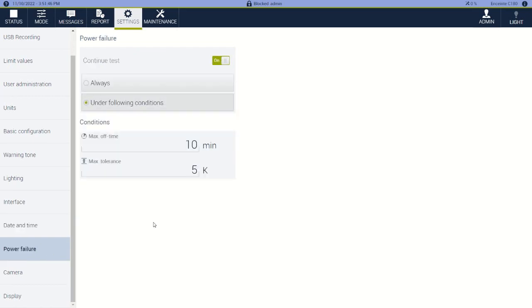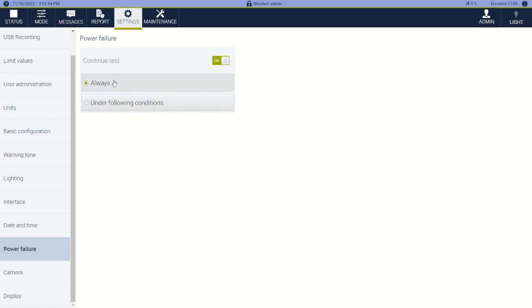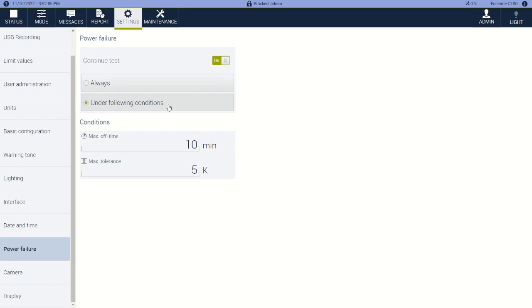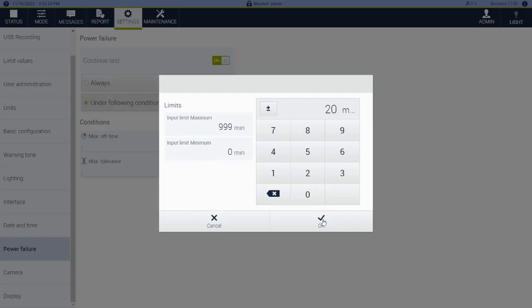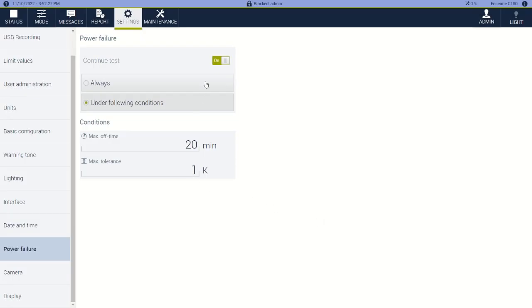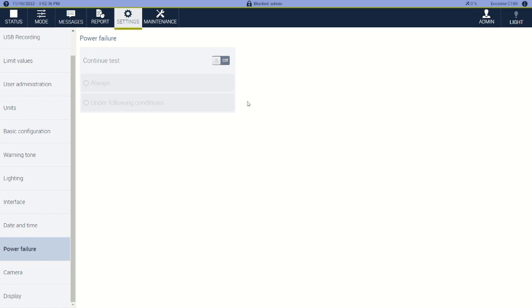For your power failure settings, we have a couple of different options. You can say always continue the test — so if you lost power and you gain power again, continue the test right where it was. Or, because of possible quality issues or procedures, say only continue the test under the following conditions: if the maximum time off was less than or equal to 10 minutes, or if the test space deviated less than 5 Kelvin. This could be changed to maybe 1 Kelvin and 20 minutes, or whatever the case may be. Or if you lose power for any reason that might invalidate the test due to your procedures, you can just say never continue the test and you'll have to restart. But this gives you a little bit of flexibility.